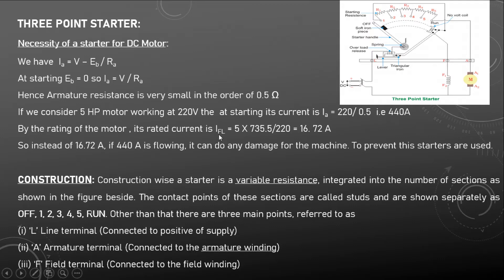By the rating of the motor, the rated current equals 5 HP converted: 5 × 735.5 divided by 220, giving a rated current of 16.72 amps. Just imagine — the motor is designed for 16.72 amps, but when you switch it on, starting current may reach 440 amps, which can cause serious damage. To prevent this, we use starters.